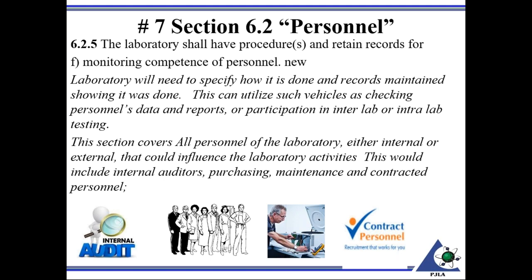Another thing is personnel. The 2017 standard is less repetitious. It says all personnel of the laboratory, either internal or external. So if you're using contract personnel, this would include them. A couple of things I like to key on: for example, if your internal auditor is an internal employee, they need to be authorized to do so, and you would have to define the competency requirements for an internal auditor. Folks that are doing purchasing, involved in the acquisition of critical supplies, perhaps equipment or calibration services. Other items would be anyone working on maintenance of any equipment. And as stated before, if you do utilize contract personnel, these same requirements would apply.